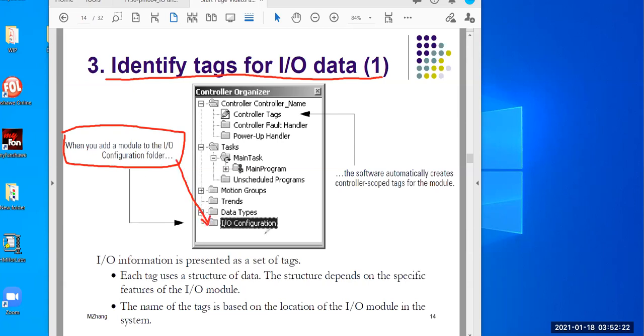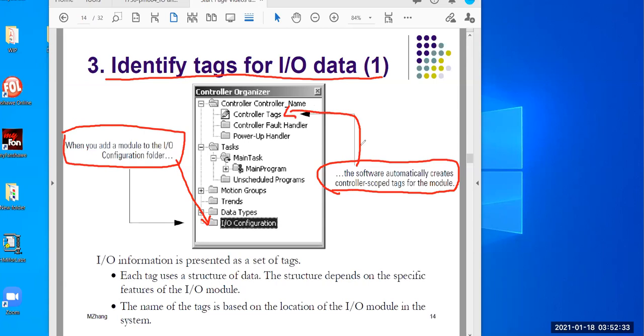When you add an I/O module underneath the I/O configuration folder, Studio 5000 or RSLogix 5000 automatically generates a tag at the controller tag level. Note that this is different from a program tag, which is local. After the software creates a tag, you can access the input/output information, presented as a set of tags, and each tag uses a structure.